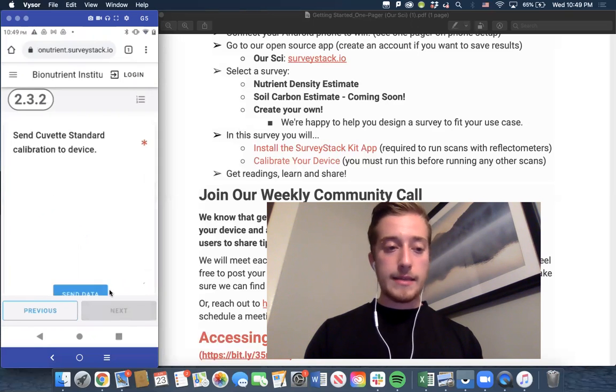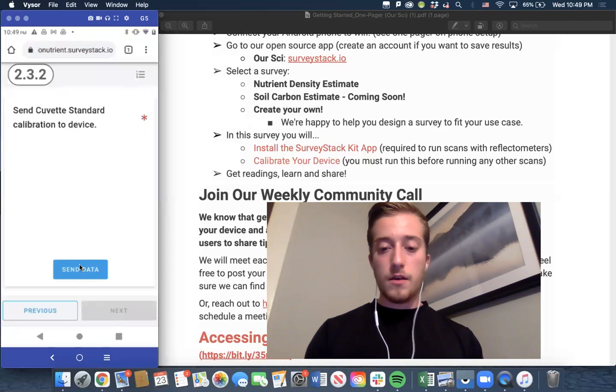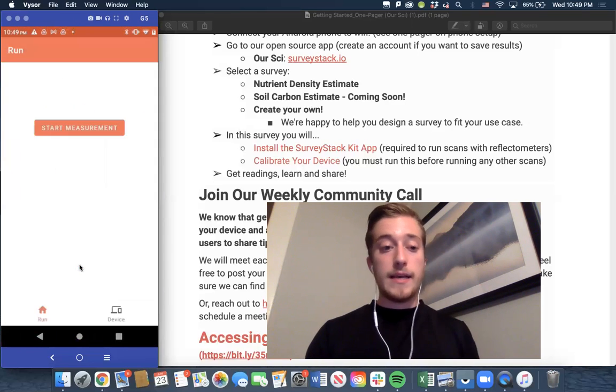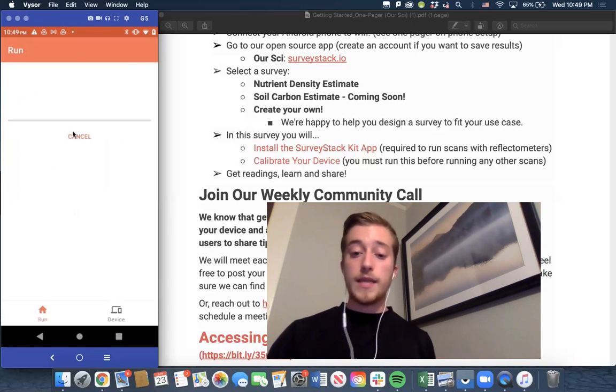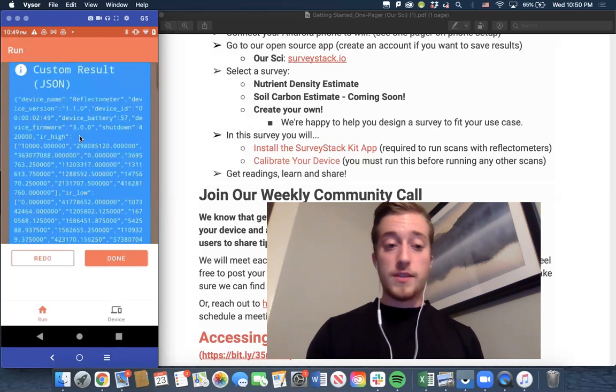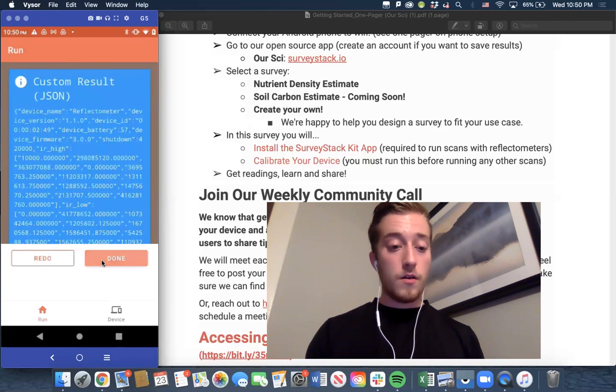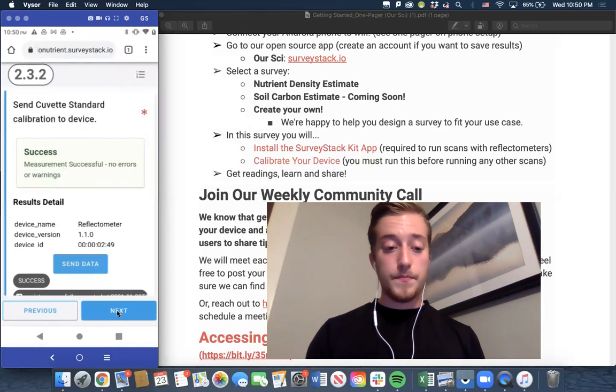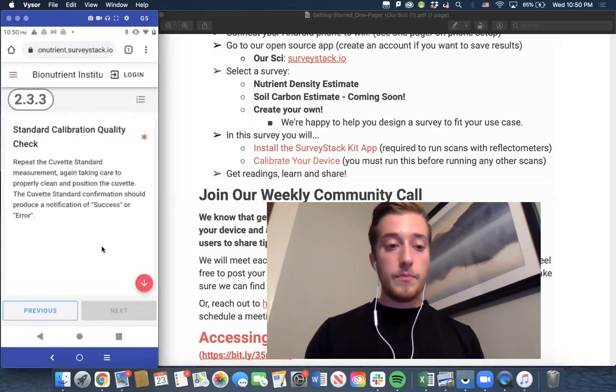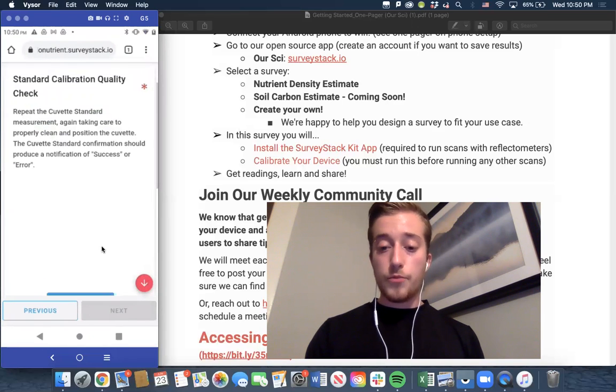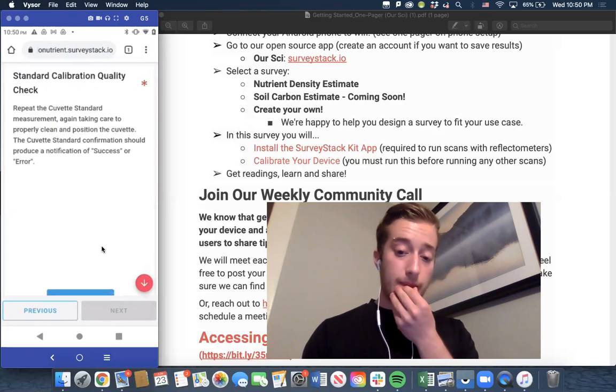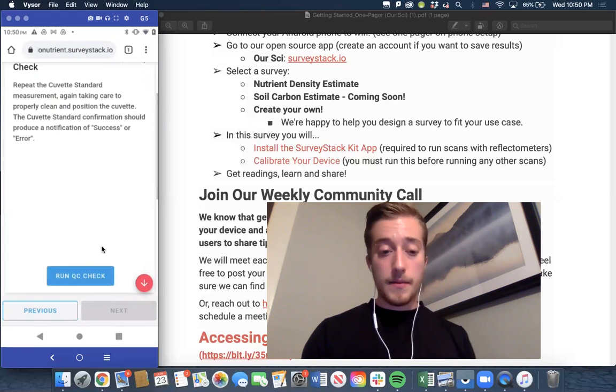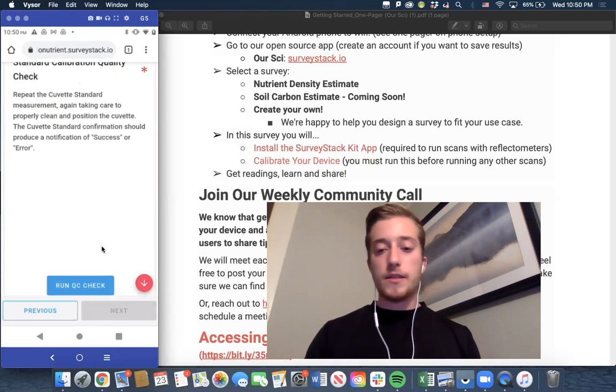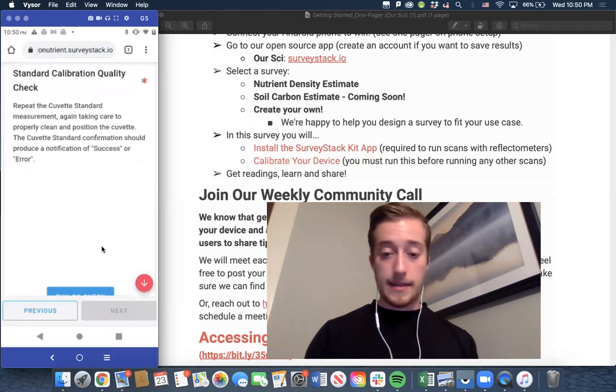Great. I'm going to click next. And same as the open blank, I'm going to send my data to my device. So it saves this calibration, start measurement, and I'll get that blue JSON. So it's just saving this custom result to my device. I'll click done, and I have a success. The final step to calibration, which again you should do every time you turn this on, essentially at the beginning of a day, is just making sure that you get a quality check success.